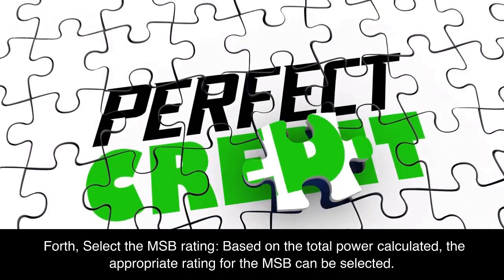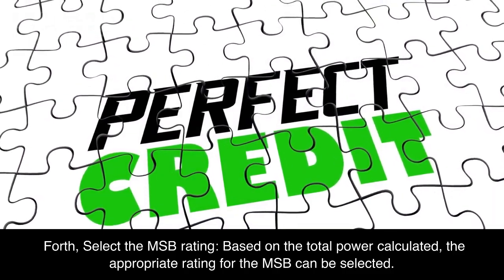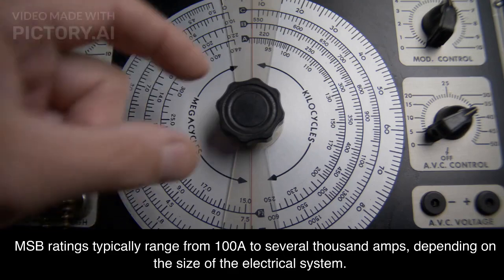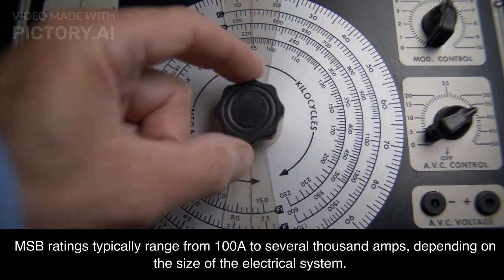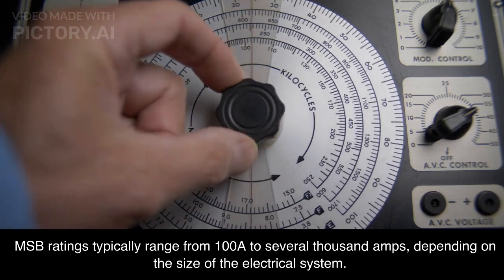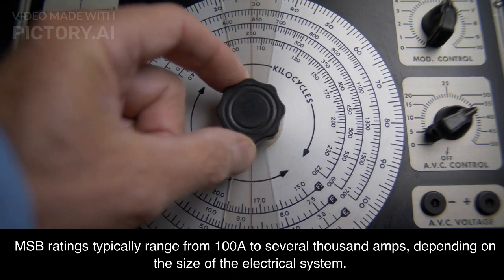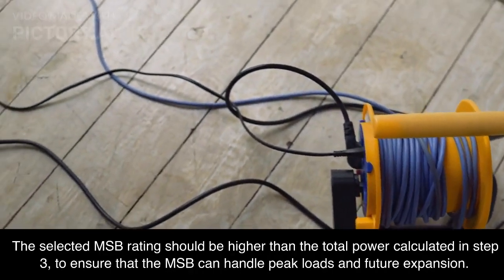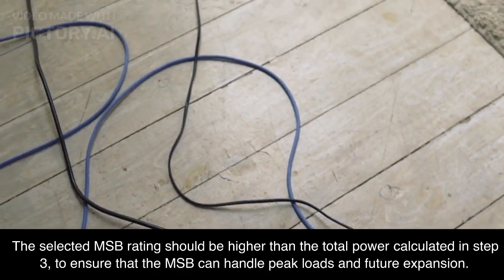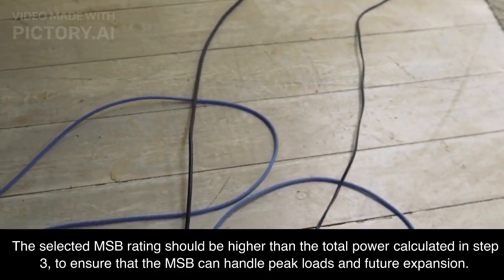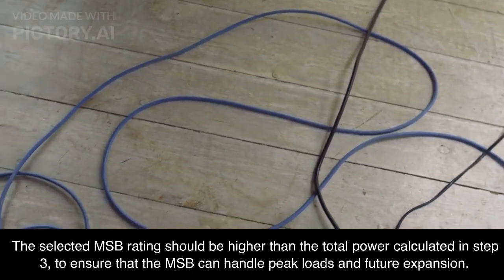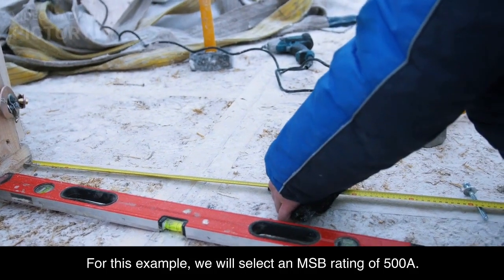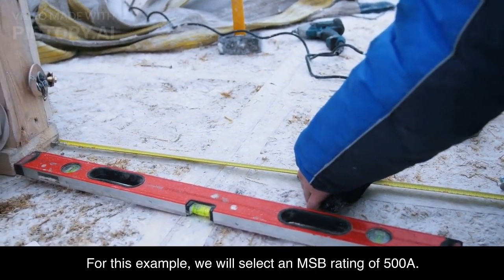Fourth, select the MSB rating. Based on the total power calculated, the appropriate rating for the MSB can be selected. MSB ratings typically range from 100A to several thousand amps, depending on the size of the electrical system. The selected MSB rating should be higher than the total power calculated in Step 3, to ensure that the MSB can handle peak loads and future expansion. For this example, we will select an MSB rating of 500A.